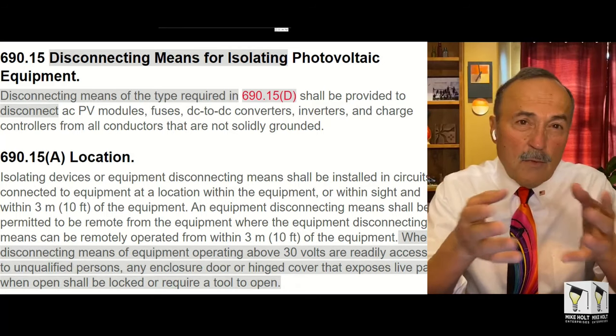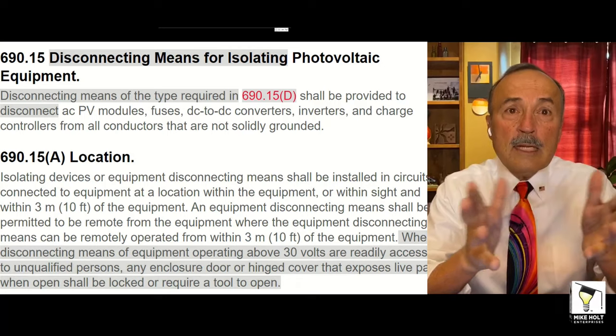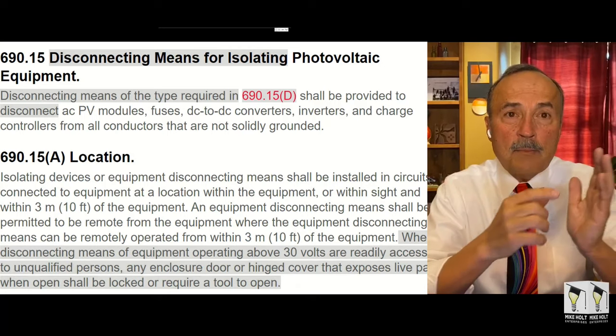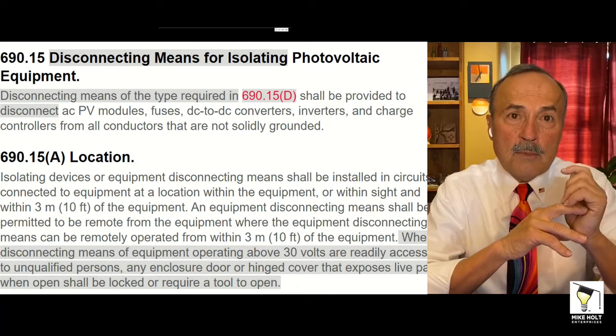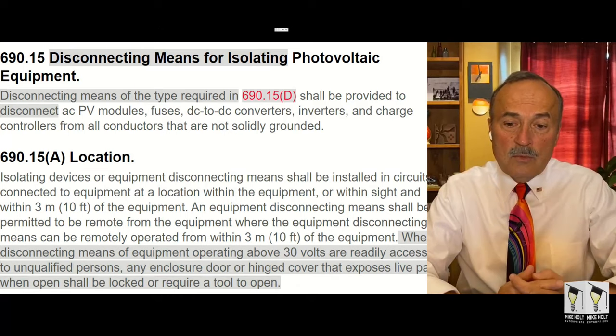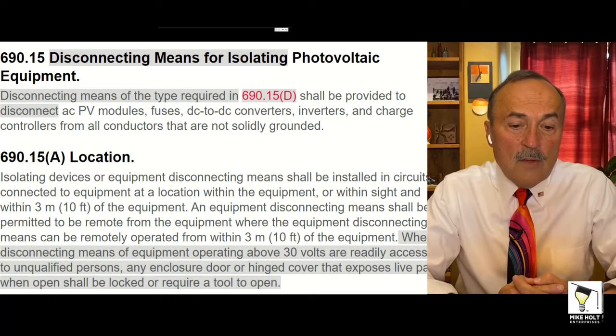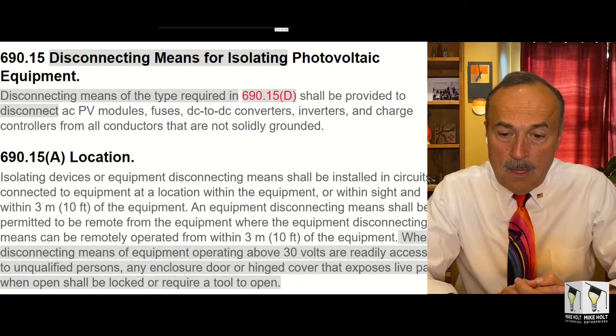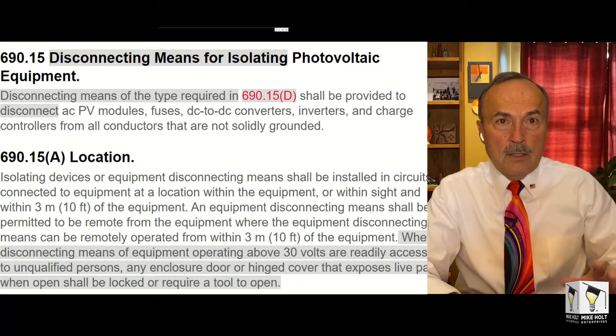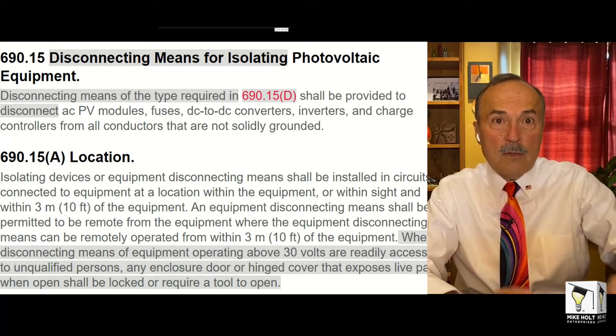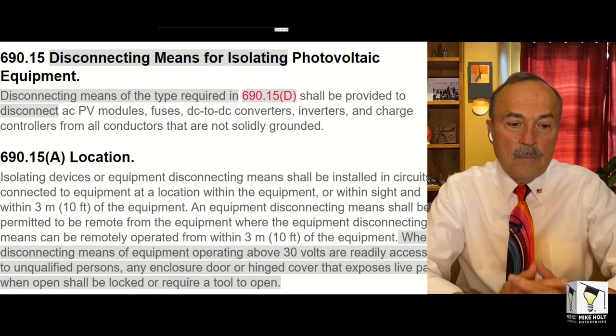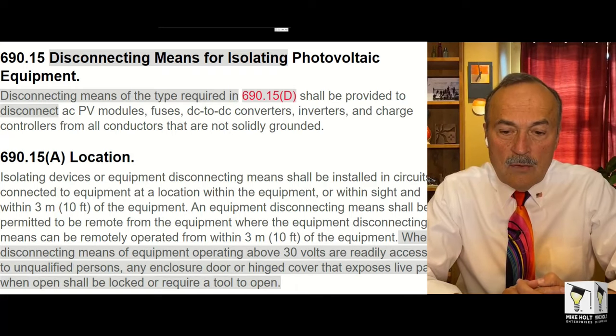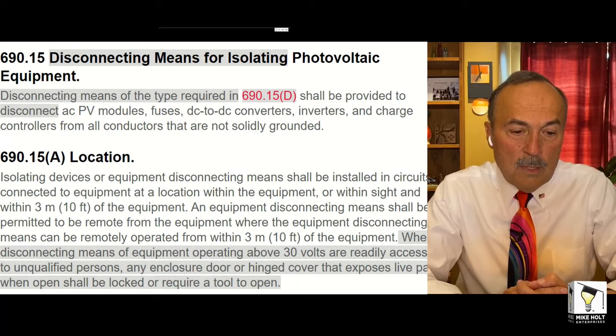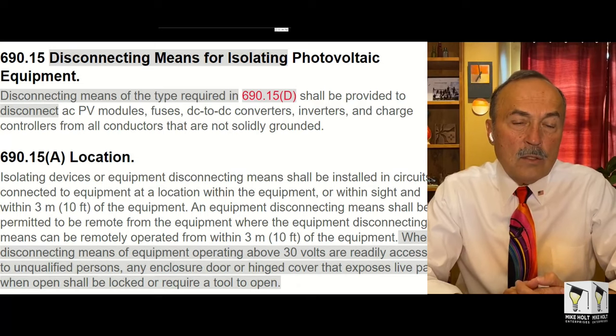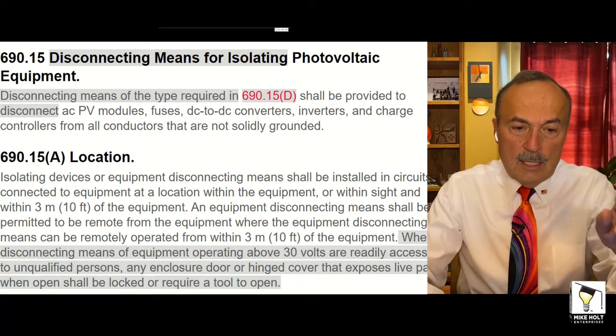And I've heard people tell me that basically it's going to be an app. You take your phone, you have an app on there, boom, you turn off the power to that piece of equipment. Here's what the 2020 change was. Where disconnecting means of equipment operating over 30 volts are readily accessible to unqualified persons, well, that means that you can walk right up to it, like at ground level, where a child can get to it, any enclosure door or hinge cover that exposes live parts when open shall be locked or require a tool to open. So that was a change that was made.